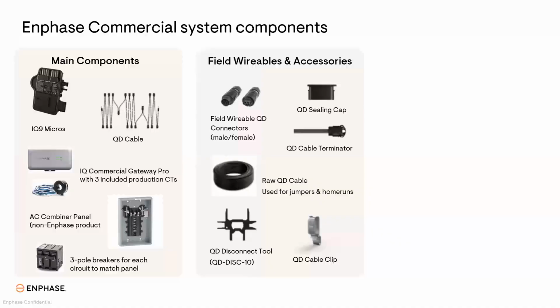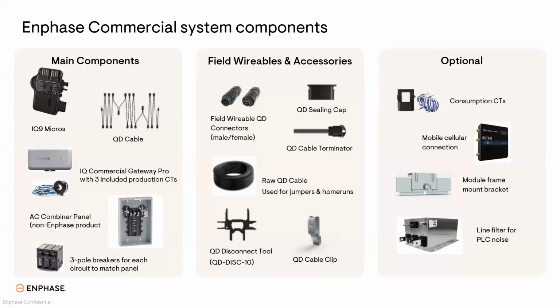Then we have our field wirables and accessories. We have field wirables, male and female. We have raw QD cable for jumpers and home runs. We have QD terminators, which terminate each end of that QD cable. Like I mentioned, if you've already installed Enphase residential before, you're looking at this and thinking, it's pretty much exactly the same. That's because it is, it's just a couple extra wires, and the installation process is fairly identical. Lastly, we have our optional components that can get added depending on the design and or site requirements.